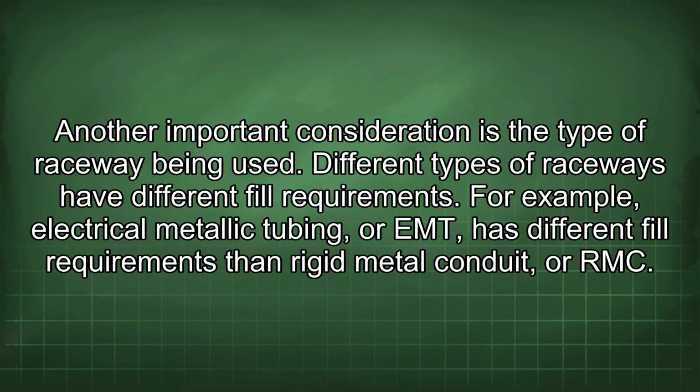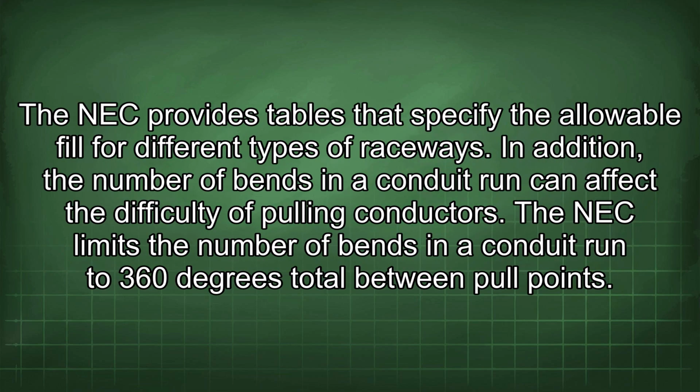Another important consideration is the type of raceway being used. Different types of raceways have different fill requirements. For example, electrical metallic tubing, or EMT, has different fill requirements than rigid metal conduit, or RMC. The NEC provides tables that specify the allowable fill for different types of raceways.